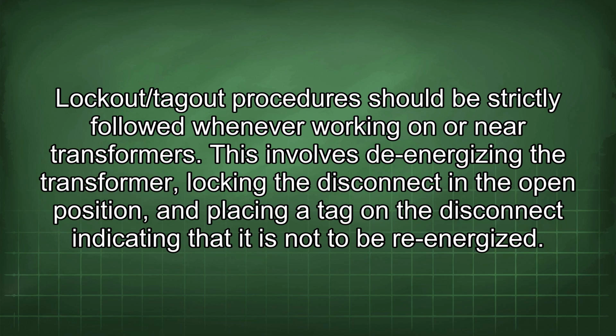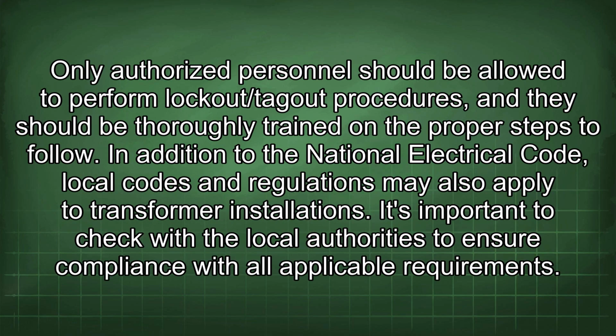Lockout/tagout procedures should be strictly followed whenever working on transformers. This involves de-energizing the transformer, locking the disconnect in the open position, and placing a tag on the disconnect indicating that it is not to be re-energized. Only authorized personnel should be allowed to perform lockout/tagout procedures, and they should be thoroughly trained on the proper steps to follow.